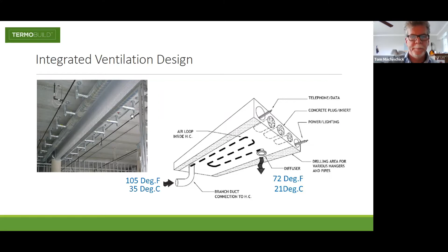So what does an integrated ventilation system buy you? When you compare a standard building to a building that has integrated ventilation design, you're actually saving from $10 to $50 per square foot. And this savings comes from the reduction in size of the HVAC system itself, the elimination of a large amount of ducting, such as perimeter ducting that is required in a standard building to assure that the outside temperatures don't seep through the building envelope into the indoor environment.